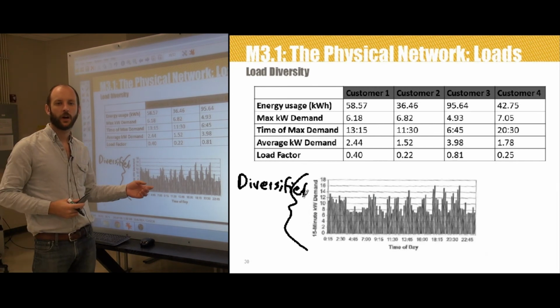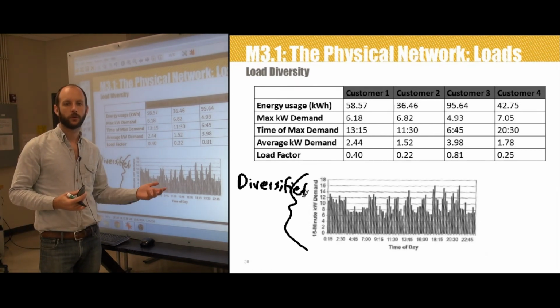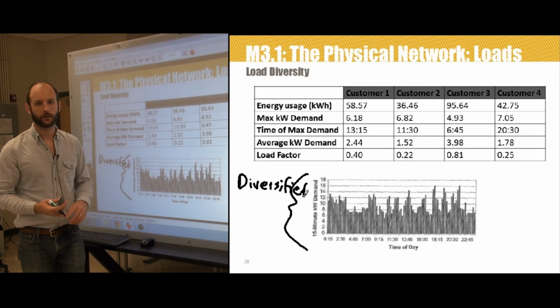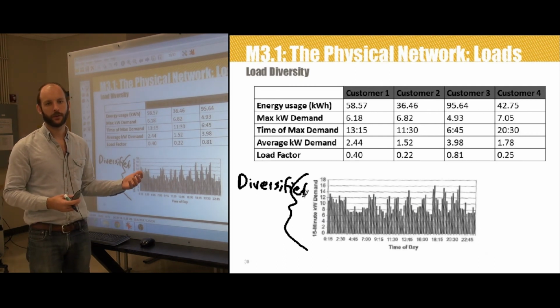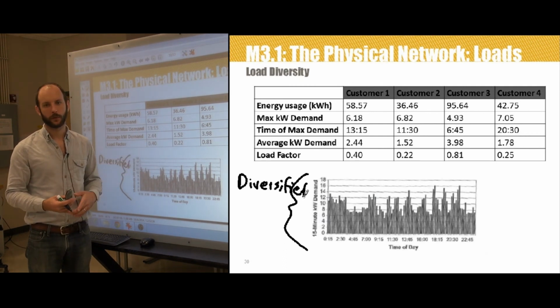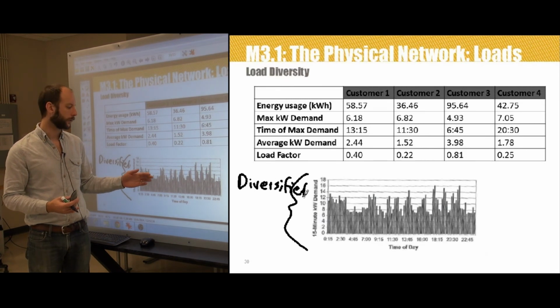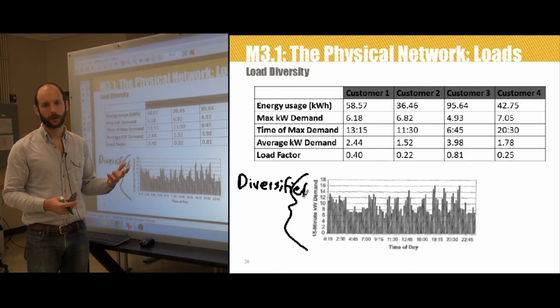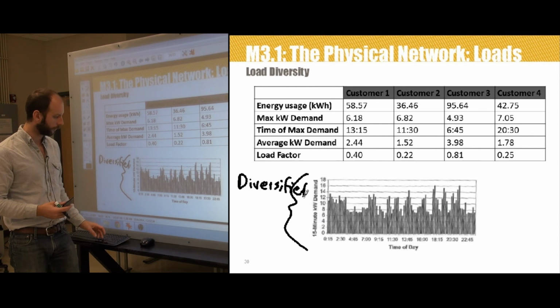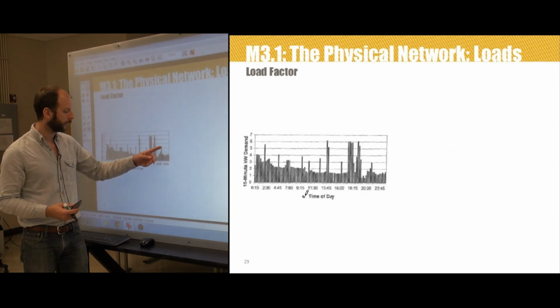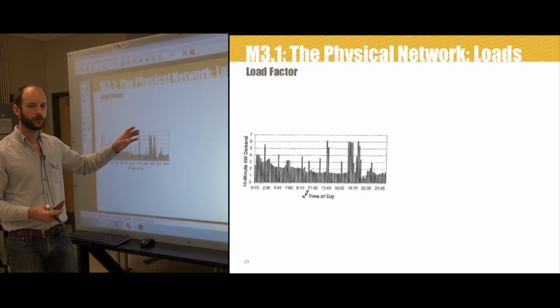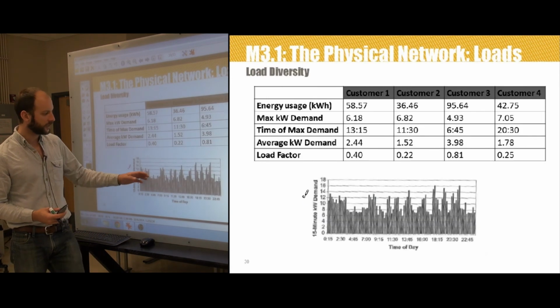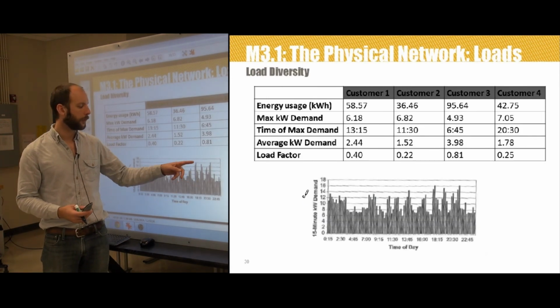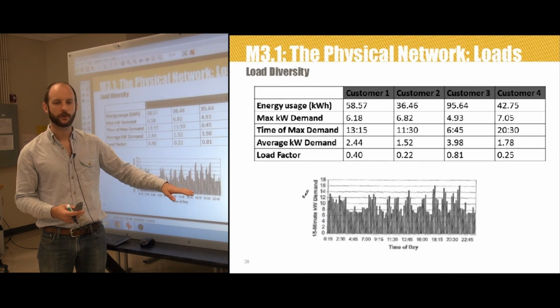And it gives data on the loading of the individual transformer used to serve that particular customer grouping. You'll notice from this sample data presented for these 4 customers that the demand curve is really beginning to smooth out as compared to an individual customer's demand curve. I'm just going to flip back real quick. Look how peaky this one is. There are huge excursions. In this one, there are still excursions, but the magnitude of the excursion compared to the average level has been reduced.